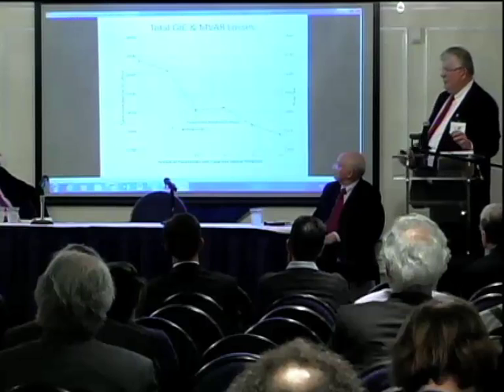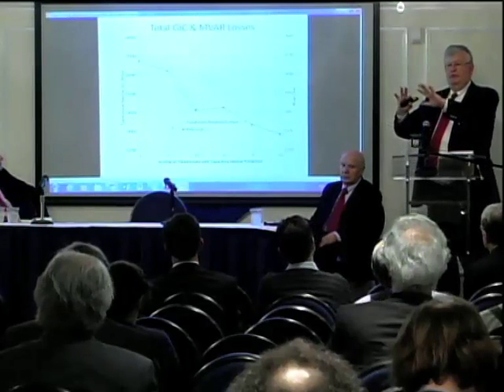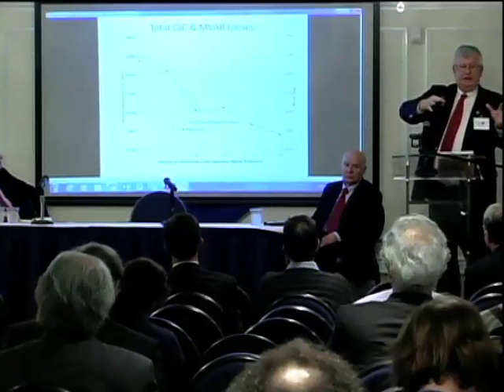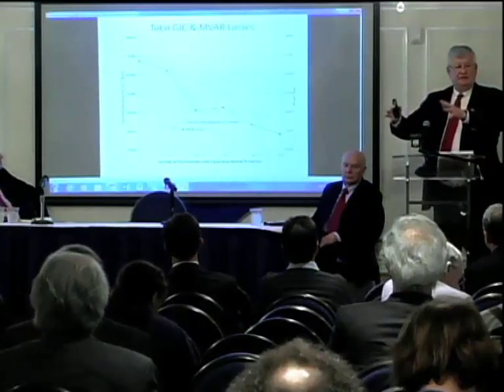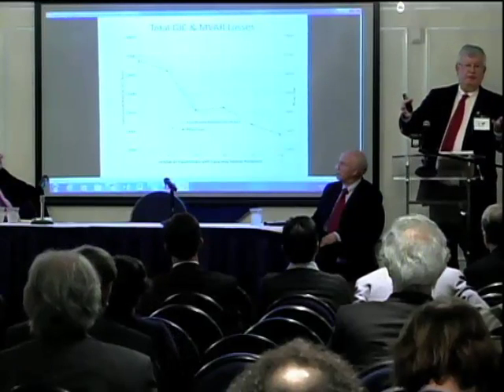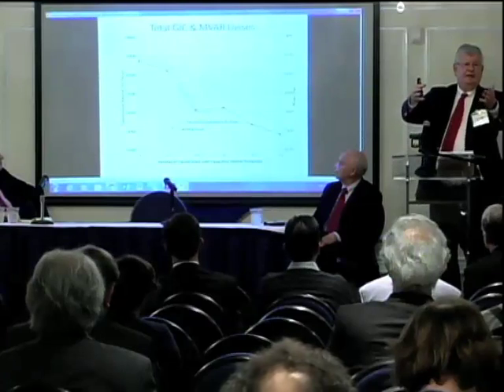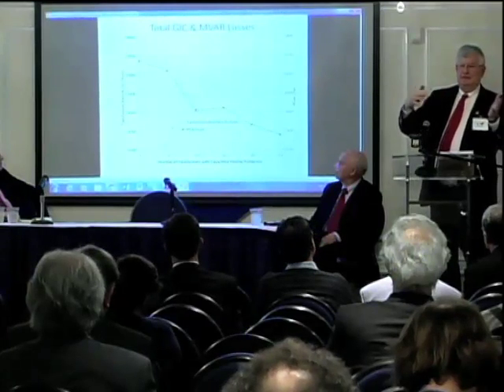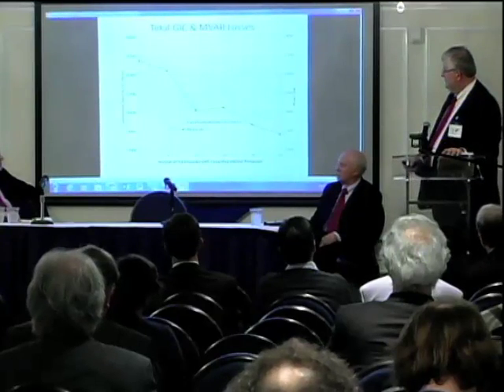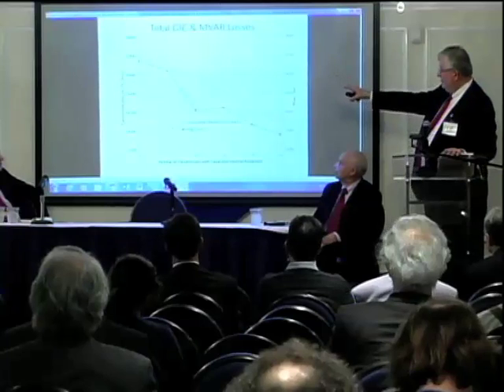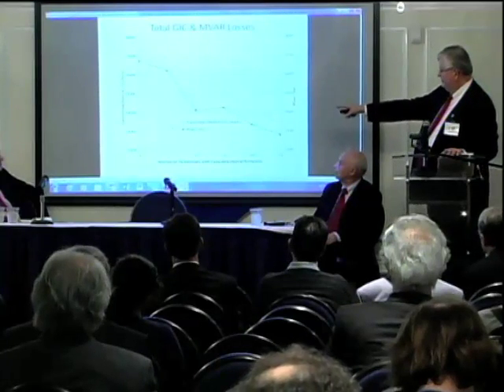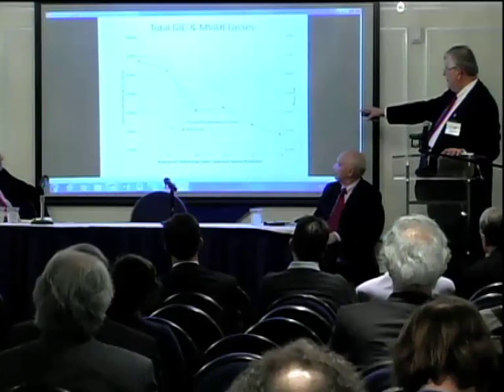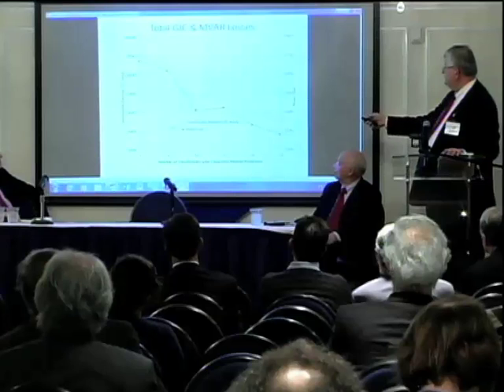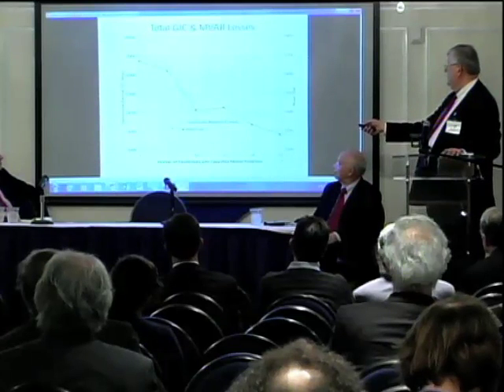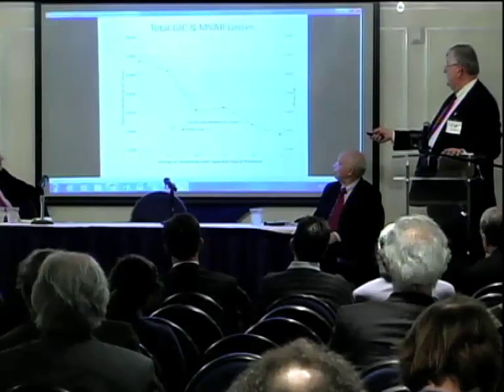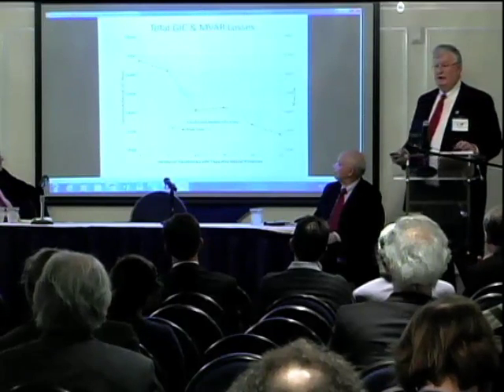So we simulated putting current blocking devices in the grid in Wisconsin, and we have a partnership that we're working with ATC in Wisconsin, so they've given us actual transformer and line data and so forth, and so we did this. And you can see what happens the more blockers you put in. This is only 25. You can see the total GIC going down in the system, and you can see the megavar loss going down.